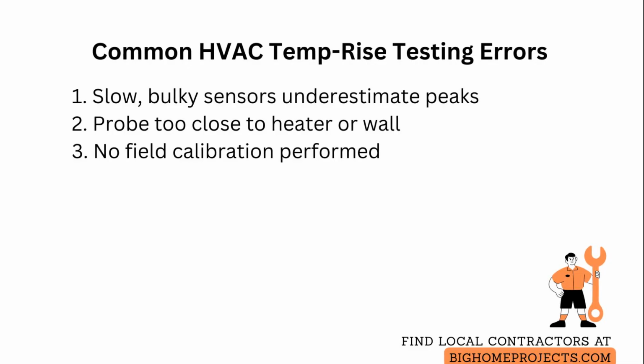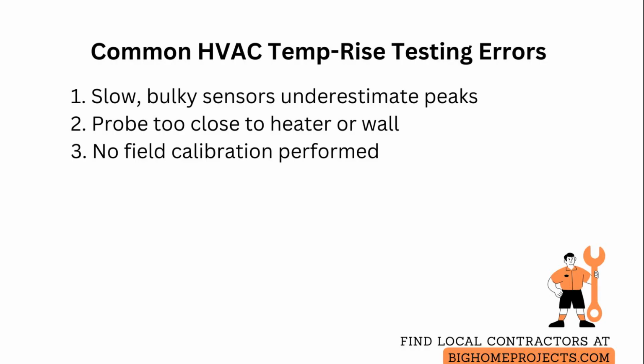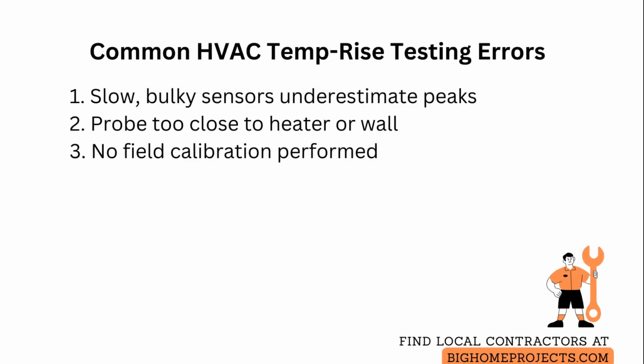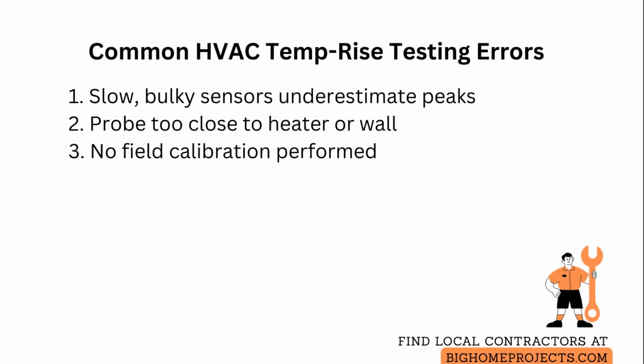A third problem is failing to verify sensor calibration and assuming factory accuracy. Resolve this by performing a field 2-point calibration against an ice water reference and a warm bath or calibrated standard thermometer and log corrections applied.